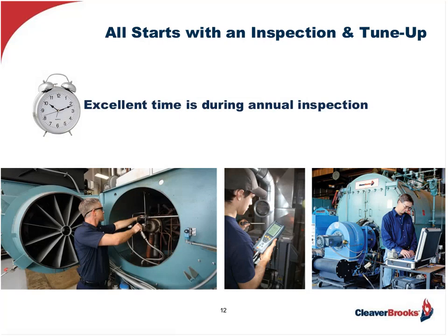What do I do about all this? It all starts with an experienced service technician inspecting the boiler — probably during its annual inspection when it's down and drained anyway — checking the waterside and fireside surfaces for cleanliness. This might mean an acid cleaning, or the fireside may be sooted and need vacuuming; it could be both. Following this, the boiler will be closed and refilled, and a complete tune-up initiated, including resetting combustion with combustion analysis throughout the burner's complete turndown range.